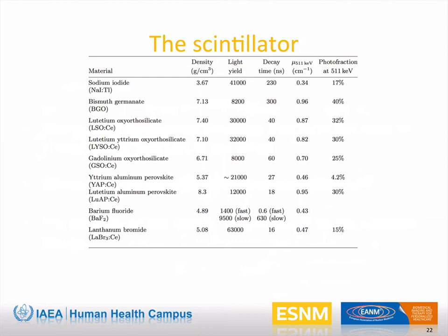This can be done in a single photoelectric interaction, followed by a fluorescence emission, or in a multiple Compton scattering process. The occurrence of one or the other modality may affect the capability of measuring the position of the first interaction as required for PET. For this reason, the relative probability between the photoelectric and the total interaction in the scintillating material, called photofraction, is also an essential feature when choosing a PET scintillator.